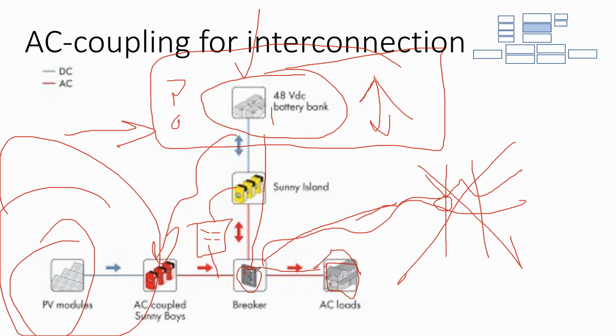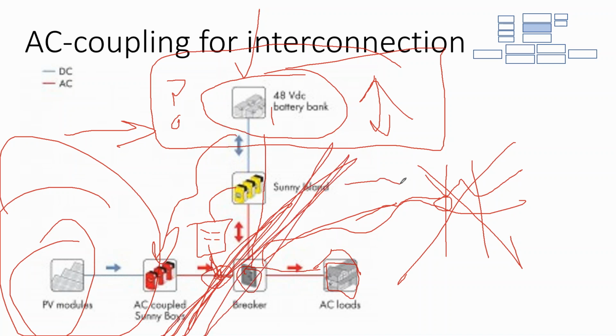On these grid-connected systems, you commonly find a requirement like the SolarEdge system that says you have to wire a critical load panel, and they don't support off-grid, only critical loads. The reason for that is they need this transfer switch so that you have a completely isolated array from the grid.